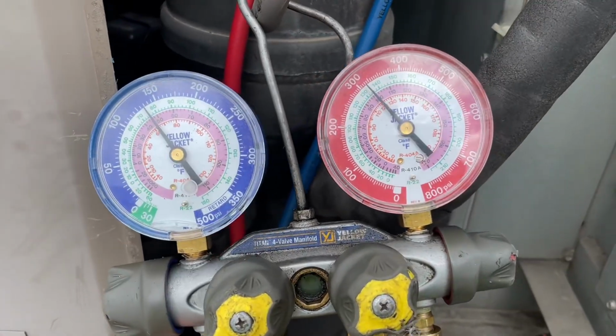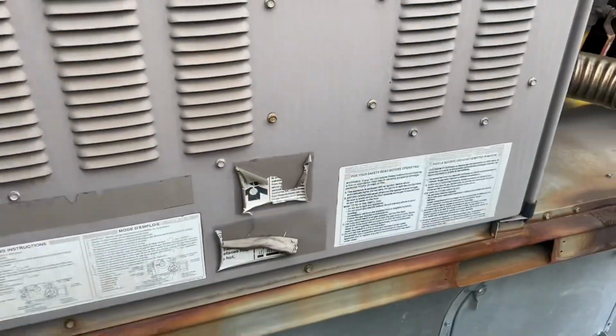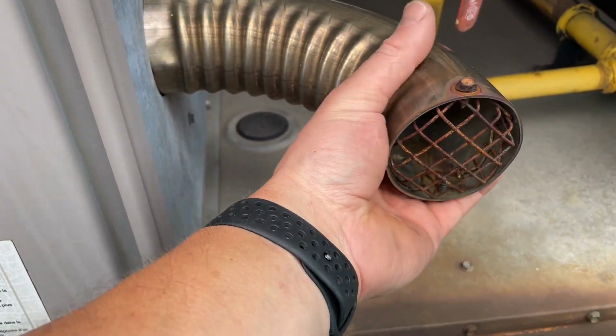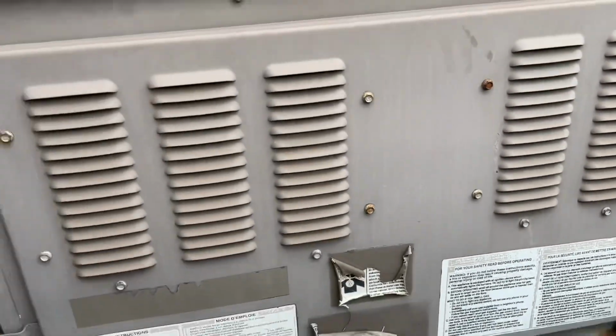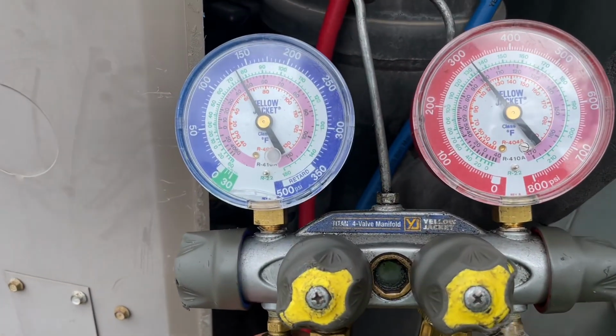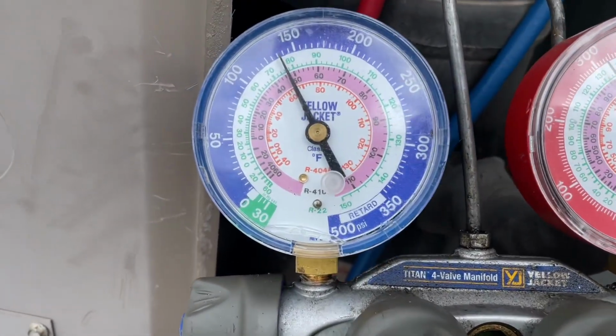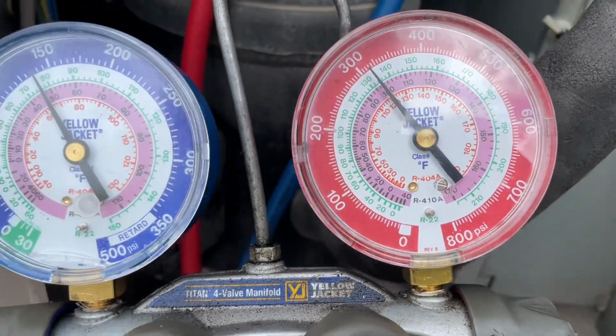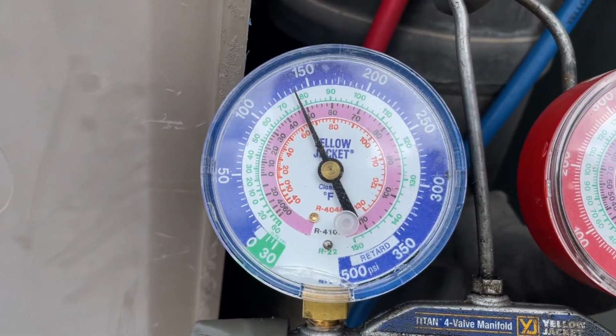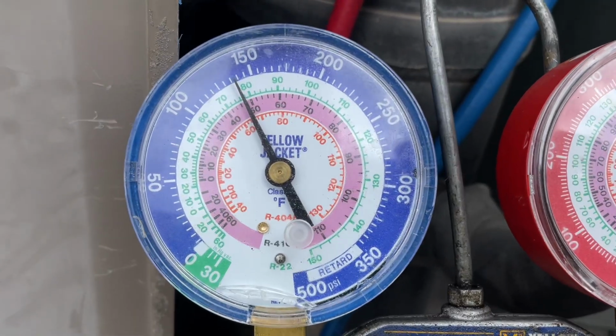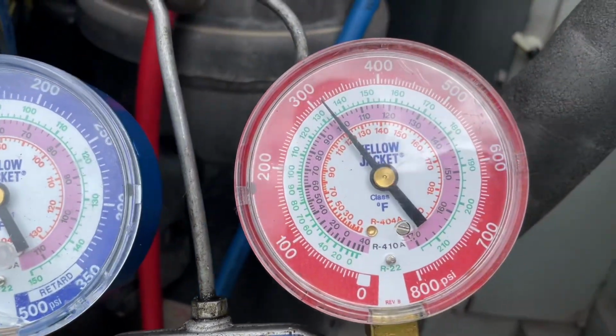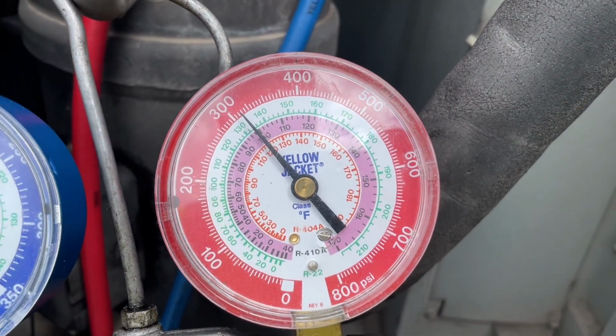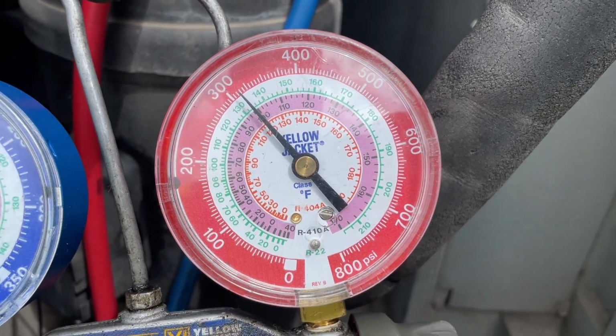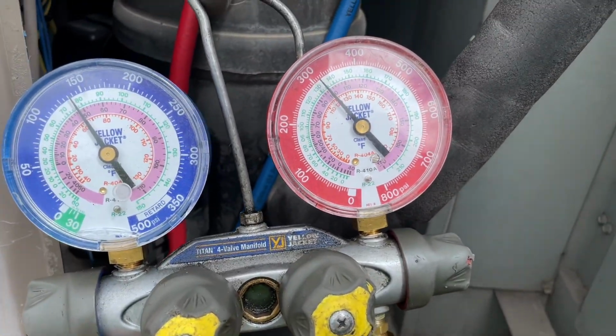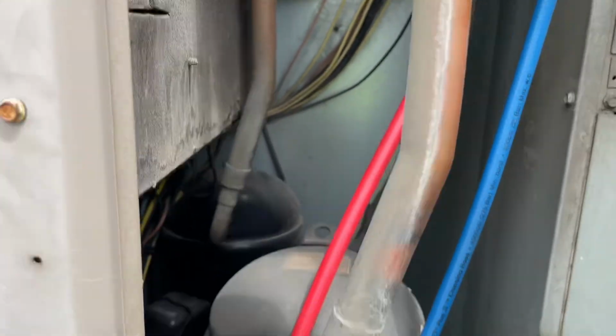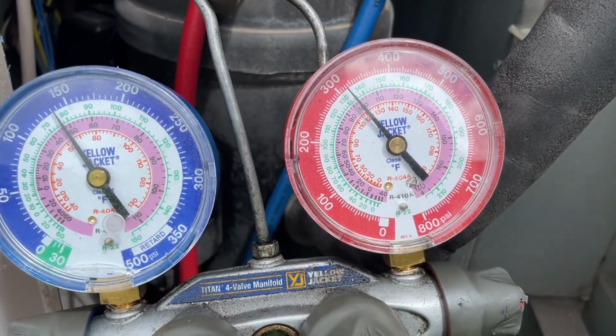Okay, guys, our cooling just kicked on. Our inducer motor is now off because we've replaced that high limit switch. We're running off 410A refrigerant here, which is our pink scale, like I always say. Anyways, we're running at about 140 PSI, which is a 48 degree evaporator. Head pressure's 315, 100 degree coil temperature. These pressures look awesome. Let's hook up second stage and we should be good here.